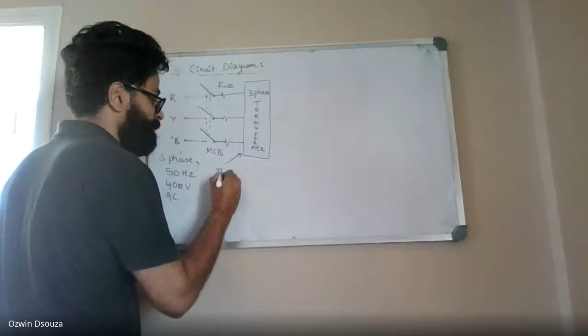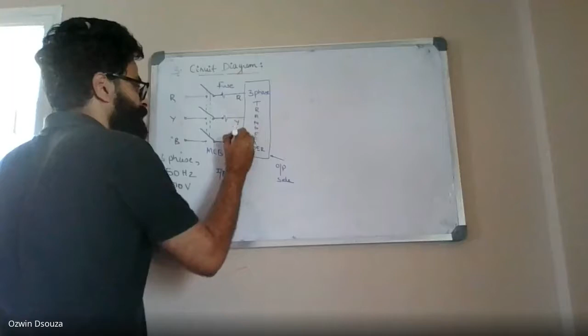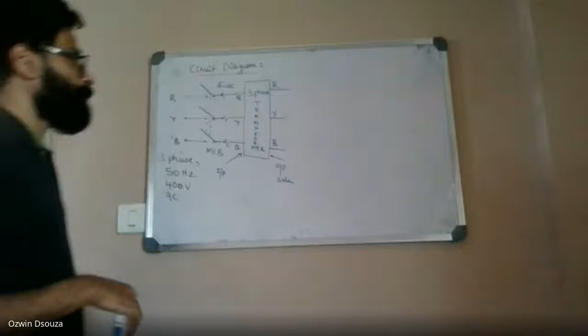3-phase transformer. Now, this is the input side of the transformer, and this is the output side. On the input side, you will have RYB terminals, and similarly on the output side you will have RYB terminals. What you have to understand is that the input R of the transformer is connected to R of the supply, Y to Y, B to B. By doing so, you can follow the right phase sequence.